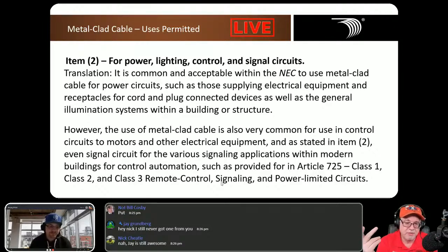It's common and accepted within the NEC to use metal-clad cable for power circuits, we do it every day. It's the main driver for electrical equipment and receptacles for cord and plug connected devices, as well as general illumination systems within the building or structure. So I can run it around the room, through the studs, to outlet boxes for receptacles, so I can subsequently plug in cord and plug connected loads, just like maybe an office that's real, with receptacles all around it, probably either conduit or MC cable.